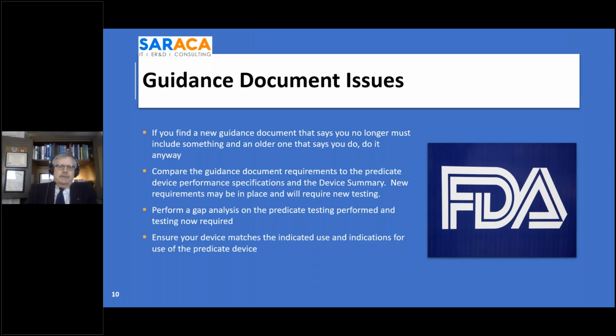But to be sure, make sure you do both or call them. Secondarily, the older guidance documents may have different requirements for performance testing. Highly recommend you do a gap analysis on the predicate testing that was performed and look at the testing that's now required. For example, on 10993-1, some of the subparts of 10993 now require new techniques and a new analysis. So you want to make sure that you do a gap analysis on the 10993 or biocompatibility testing, and make sure your testing was valid.